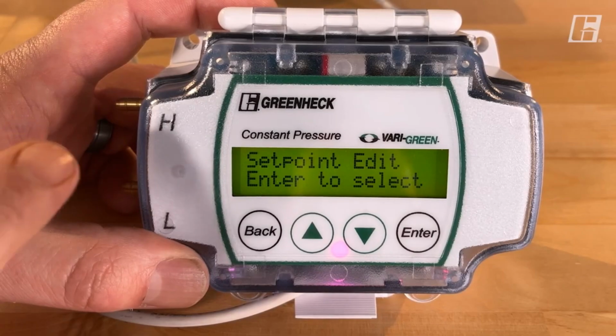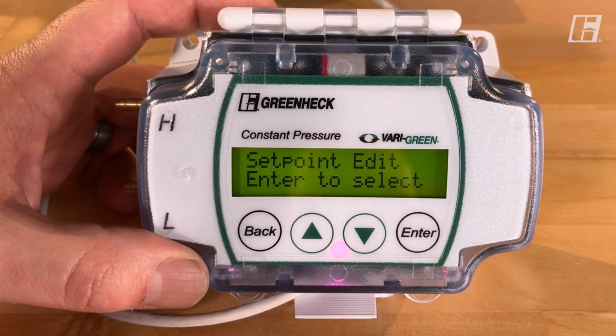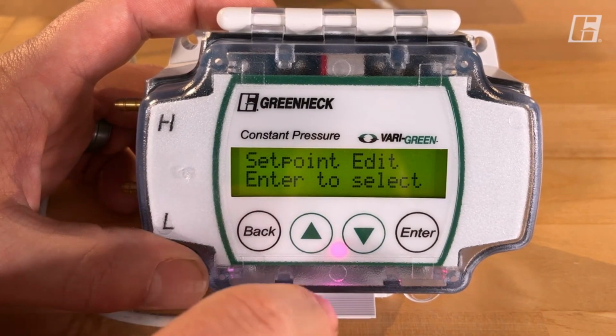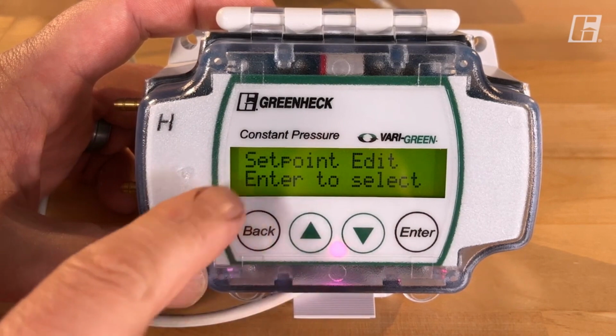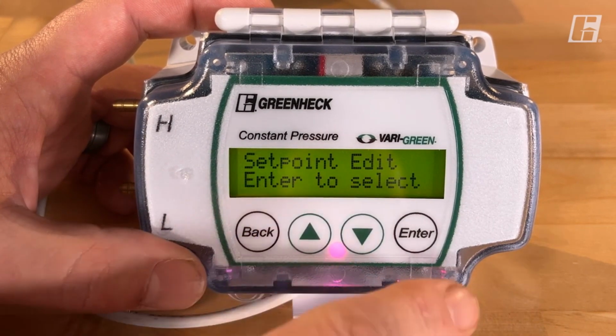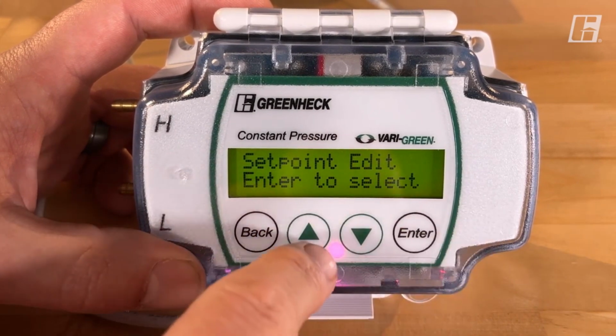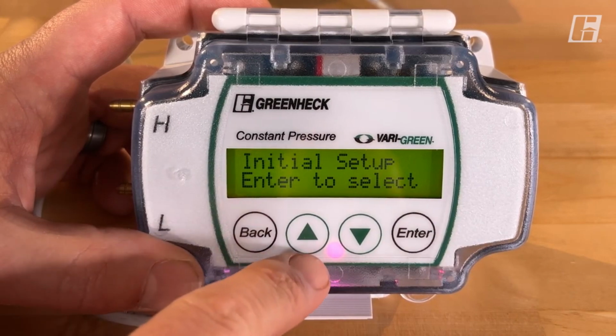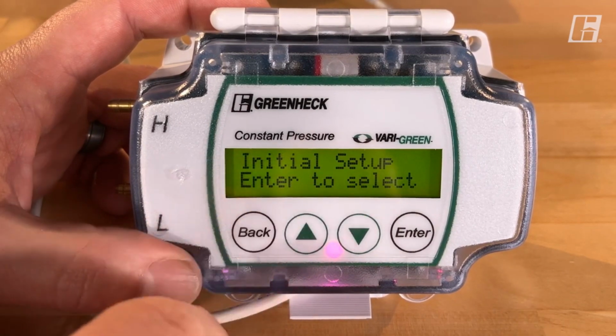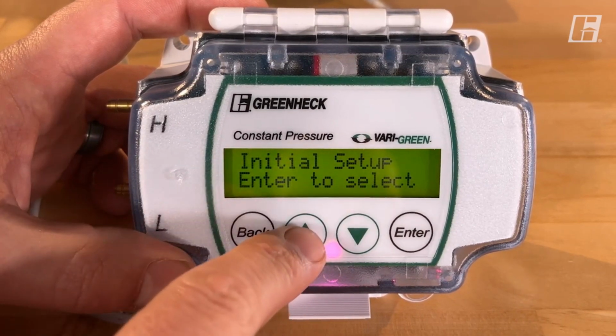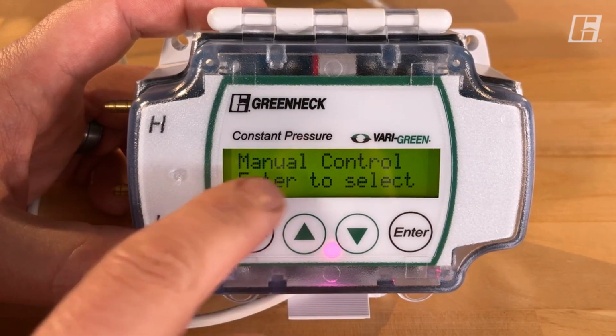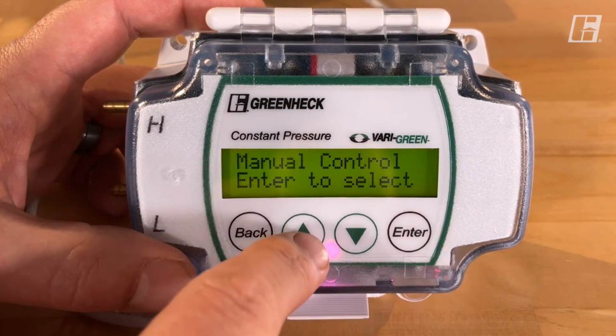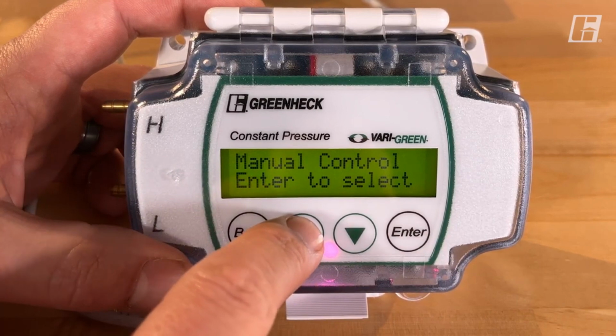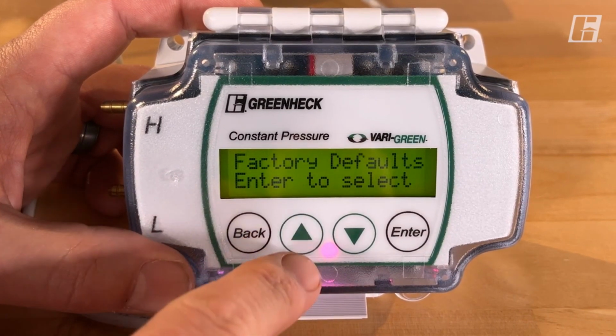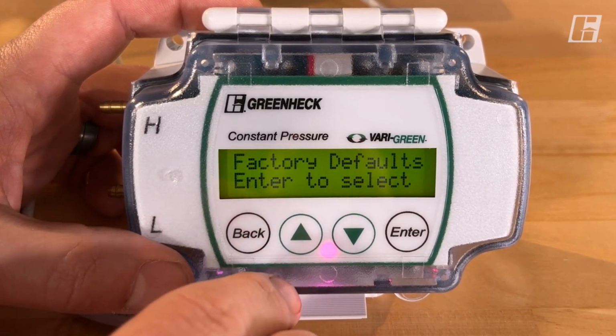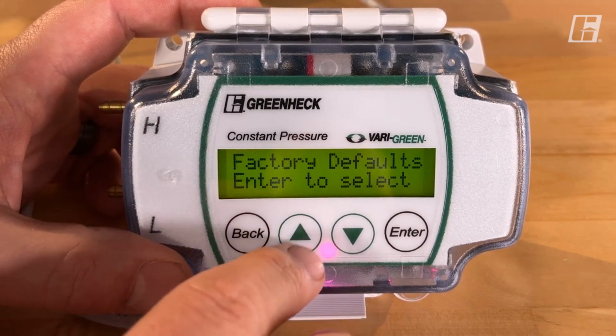There are 4 menus within the program mode, and 2 of them are the ones that we actually need to address. The first one, set point edit. This is where we're going to put in our set point. By hitting the up arrow, I can get to the initial setup menu. That's the second menu we're going to play with. The third is manual control. That just allows you to manually control the speed of your fan. And then the fourth is to reset this to factory default.